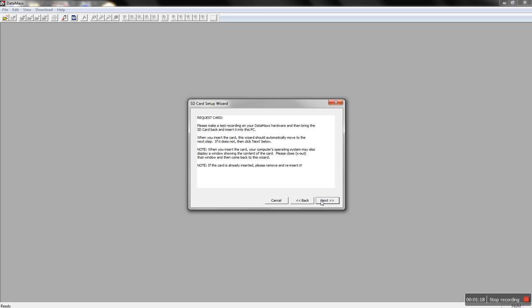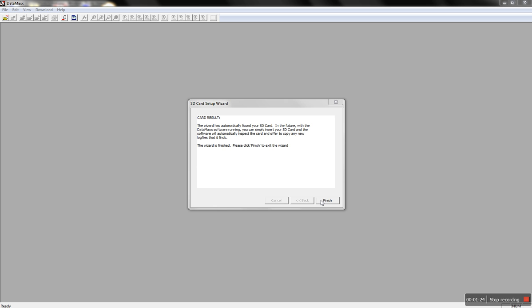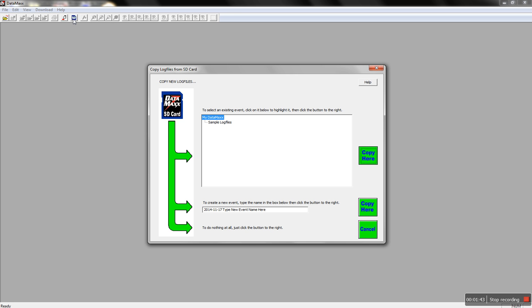Now it's asking for us to request the card, so we're going to place the SD card in. Now it automatically found the SD card for us, so we're going to go ahead and hit finish. If it did not find it, then just follow the instructions on the screen. After we have told the DataMaxx software where the SD card is, we can download the log file. Now to download the log file correctly, we want to hit this SD button. Doing it correctly is very important because it allows us to keep our log files organized and also allows us to keep the SD card cleared off.